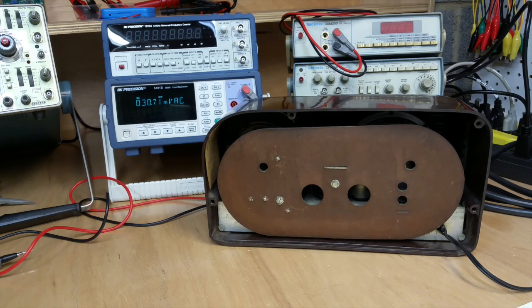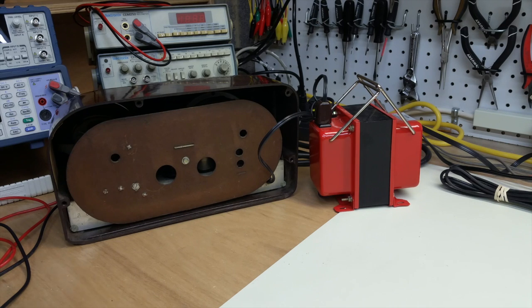So how do we work on a piece of equipment like this safely? One way to make it safer is to use an object called an isolation transformer. So this is an isolation transformer. This is a very simple unit. The thing that makes it an isolation transformer is that the secondary side is completely isolated. It has no contact with the primary side. What that means is that the reference to ground is removed from the secondary side of the isolation transformer.